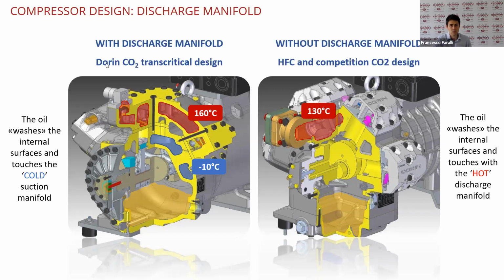And heating the oil is, let's say, a dangerous problem for CO2 because the discharge is very hot and you risk having a very high oil temperature. And of course, if the oil is very hot, the viscosity will drop dramatically. And in case of poor viscosity of the oil, you risk having a lubrication problem. On the other side, you see that the Freon compressor and also all our competitors have an internal discharge manifold. In this way, for sure, there is no separation between the hot gas discharge and the oil sump. And what you risk having is basically a higher oil temperature.